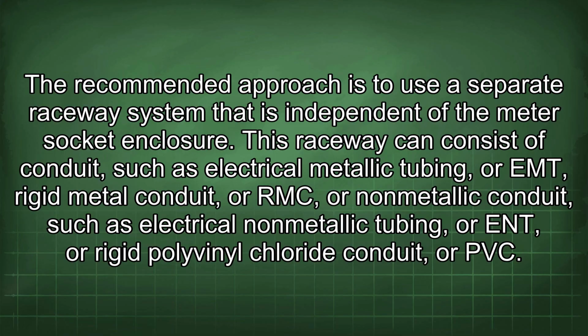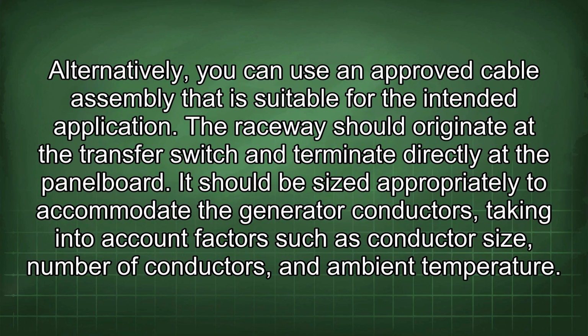This raceway can consist of metal conduits such as electrical metallic tubing, or EMT, or rigid metal conduit, or RMC, or non-metallic conduit such as electrical non-metallic tubing, or ENT, or rigid polyvinyl chloride conduit, or PVC. Alternatively, you can use an approved cable assembly that is suitable for the intended application. The raceway should originate at the transfer switch and terminate directly at the panel board.